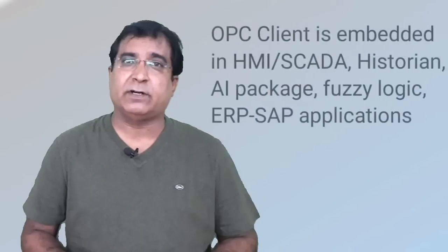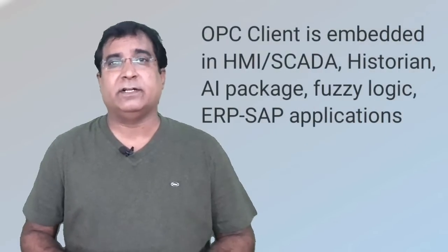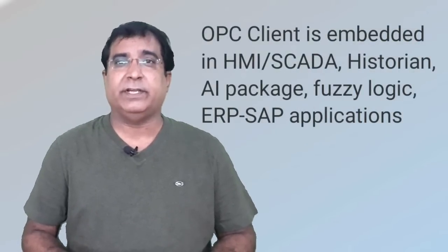There are various independent OPC servers in the market who can develop your OPC Server for hardware if the manufacturer is not able to provide. OPC Client is a two-way application software through which operator data or command requests are converted into OPC protocol and then sent to OPC Server. The response received from OPC Server is given back to OPC Client to further convert into operator application language. OPC Client is a logical counterpart of OPC Server. This OPC Client is an integral part of HMI, SCADA, artificial intelligence packages, fuzzy logic systems, ERP, SAP packages, and is embedded in these applications.